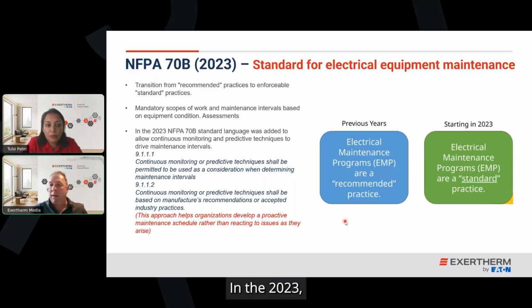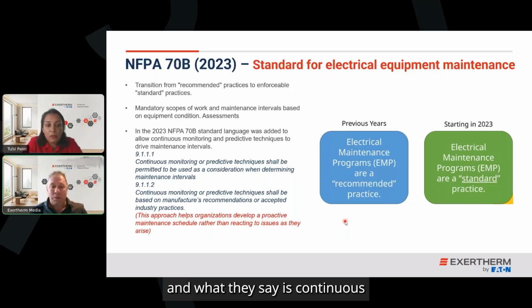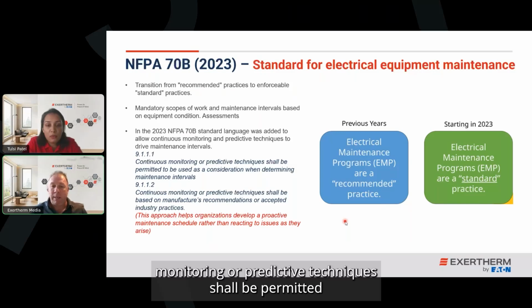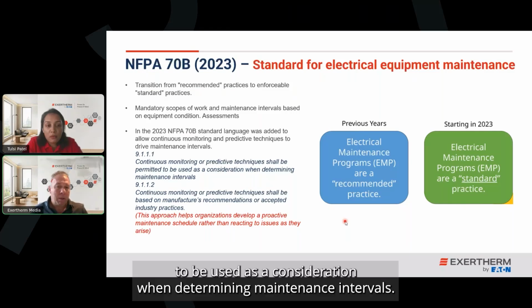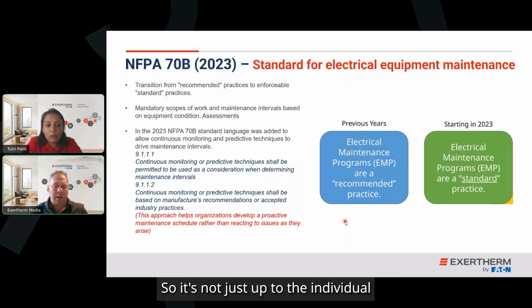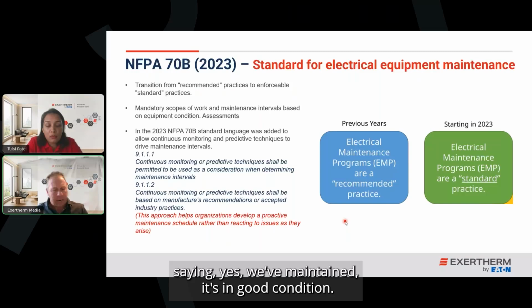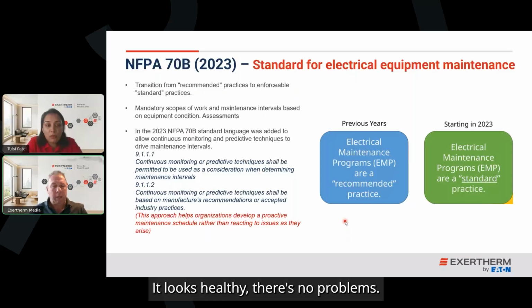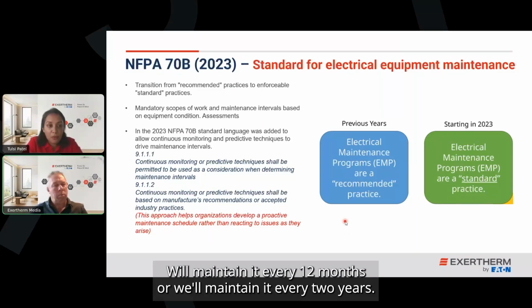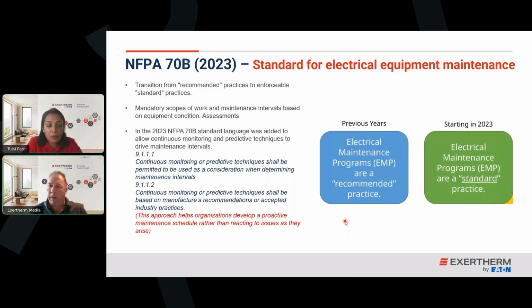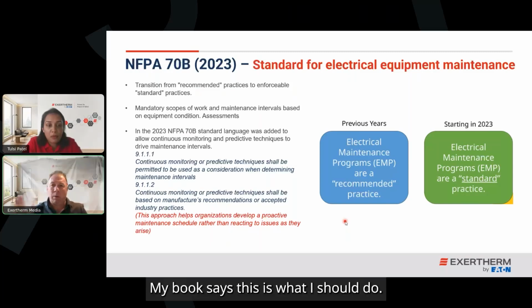In the 2023 edition of NFPA 70B, 2 clauses, 9.1.1.1, 9.1.1.2. And what they say is continuous monitoring or predictive techniques shall be permitted to be used as a consideration when determining maintenance intervals. So it's not just up to the individual saying, yes, we've maintained it, it's in good condition, it looks healthy, there's no problems, we'll maintain it every 12 months or every 2 years. Tick the box, away we go. My book says this is what I should do.